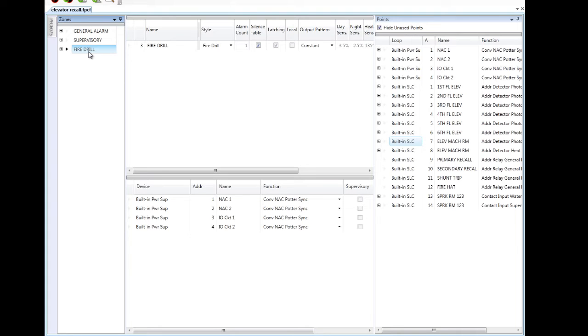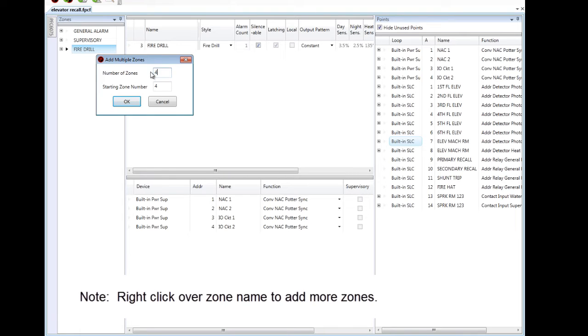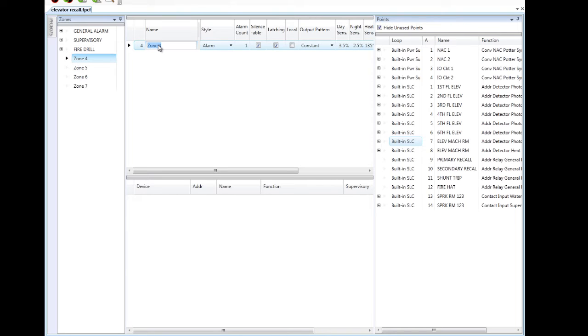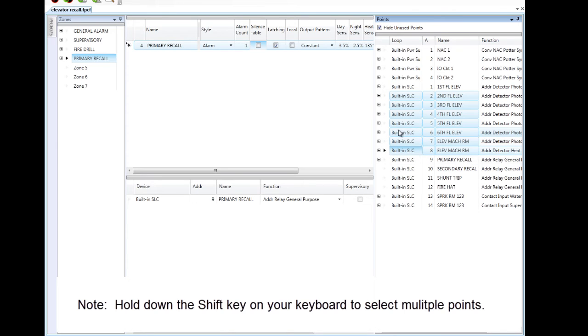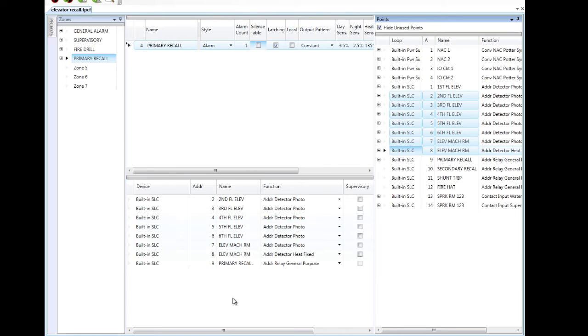For programming of the elevator recall, I'm first going to create four zones because I have four relays for this particular example. The first zone I'm going to label primary recall. I'm going to make sure this zone is non-silenceable since I'll be putting relays in it. I'm going to grab the primary recall relay. When this zone is triggered, it will recall the elevators to the primary floor of egress, which is the first floor. I want all of the elevator lobby smokes that are above the first floor — that's second through sixth floor — as well as the smoke detector and heat detector in the elevator machine room, since I would like those to recall the elevators to the first floor as well. I'm going to select all of those and drag them into this zone, and that's primary recall.